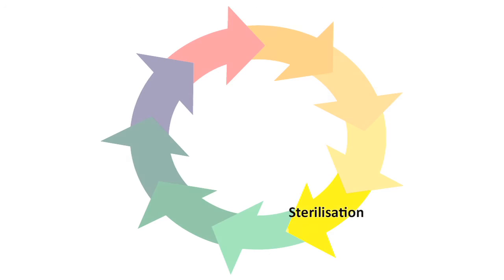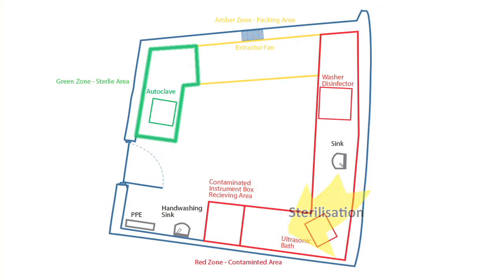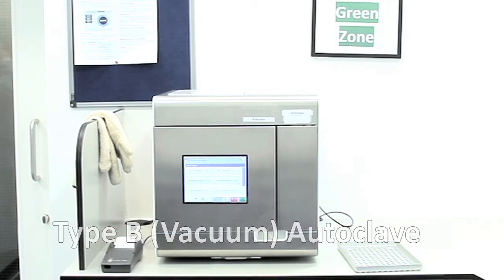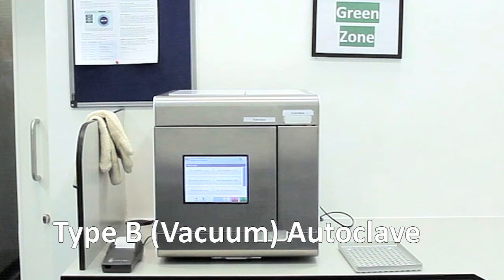We are now ready to move on to step number 6. Sterilisation. The autoclave, which is positioned in the green zone of the LDU, is used to sterilise the RIMD after decontamination and packaging. This is achieved by steam sterilisation using a vacuum autoclave. Steam sterilisation is the recommended method of sterilisation in LDUs. There are a number of required tests that must be carried out daily and weekly before using the autoclave.